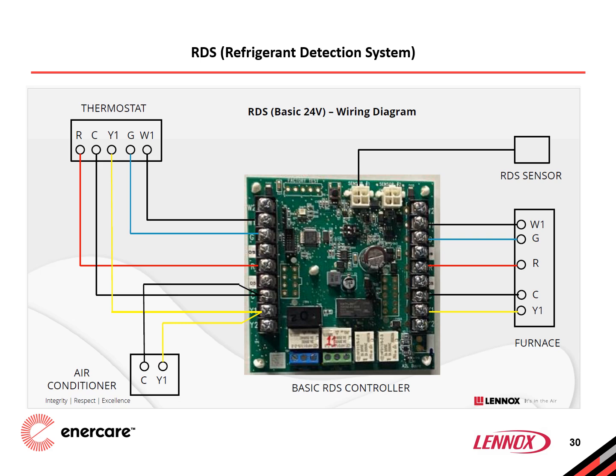Let's take a closer look at how an externally mounted Lennox RDS system integrates with a standard 24-volt thermostat. In this setup, the RDS acts as a pass-through for each low-voltage signal running between the thermostat and the appliance. Essentially, the system operates normally unless the RDS sensor detects an A2L-related fault. If that happens, it overrides the standard operation. The blower automatically switches to cooling speed, while both the burner and the outdoor unit are locked out to maintain safety.